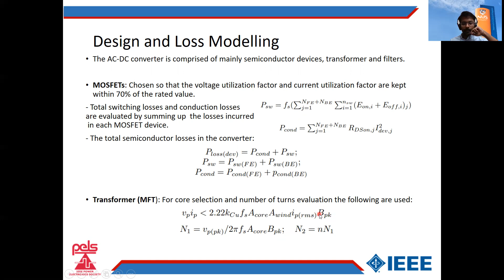The transformer's core selection has to be found by using this relation, where the power transfer should not make the flux density go beyond its peak value and should not lead to saturation. So from there we can derive the number of turns that are required for the primary, and based on the step down we can get the number of turns required for the secondary.